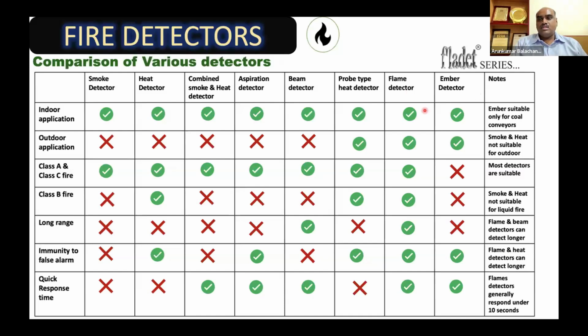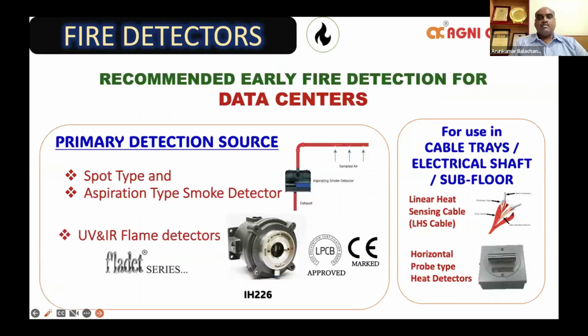So for indoor application, almost all the detectors will tick. And you can also find for outdoor application, many of the smoke detectors will not be able to cater to the outdoor applications. Similarly, for a class B or liquid fire, many smoke detectors may not be able to be used in those. So with this, we will come to the conclusion of what can be recommended for early fire detection for data centers.